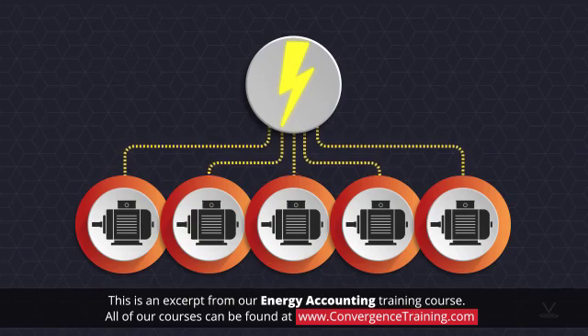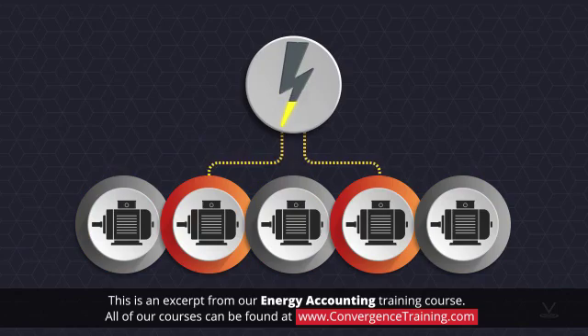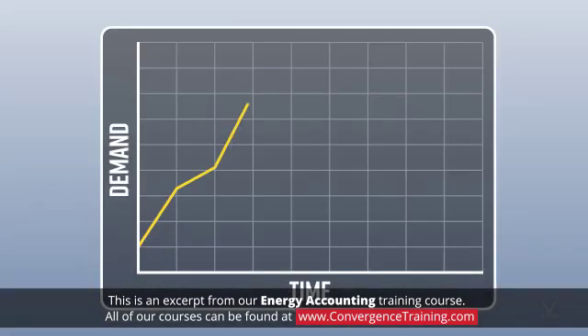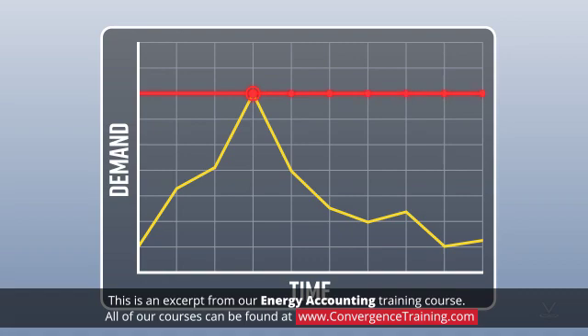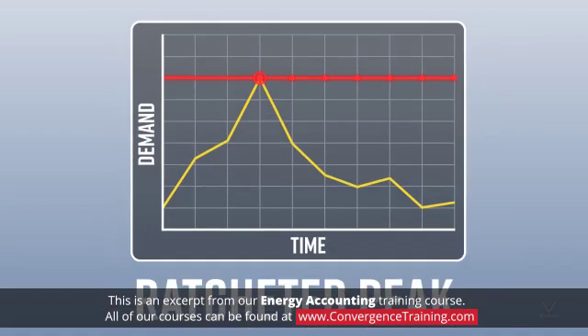By trying to avoid operating large pieces of electricity-consuming equipment simultaneously, the maximum demand can be kept down. A utility typically looks at 15-minute periods throughout a billing cycle. The demand charge per kilowatt hour is based on the maximum demand period in the cycle, and that charge is applied to all kilowatt hours consumed in the billing cycle. The practice of basing the demand charge on the maximum demand period in a cycle is called a ratcheted peak.